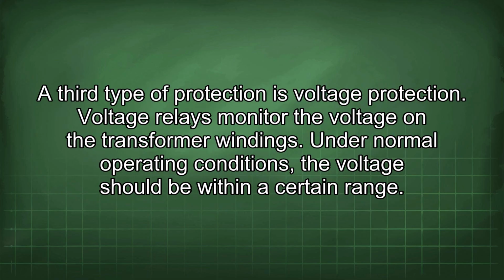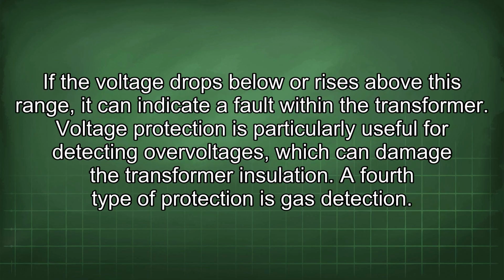A third type of protection is voltage protection. Voltage relays monitor the voltage on the transformer windings. Under normal operating conditions, the voltage should be within a certain range. If the voltage drops below or rises above this range, it can indicate a fault within the transformer. Voltage protection is particularly useful for detecting overvoltages, which can damage the transformer insulation.